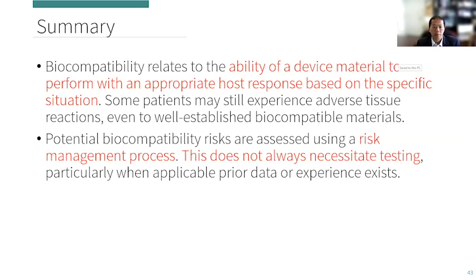And more recently, biocompatibility risks are assessed using a risk-based approach and a risk management approach, which does not always necessitate testing, especially when you have prior applicable data or experience that can help inform the potential biological safety risk for that material or device.